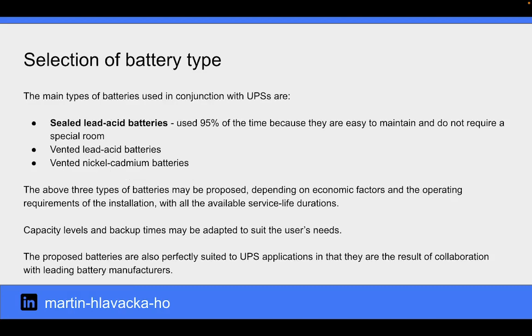The main types of batteries used in conjunction with UPSs are sealed lead acid batteries, which are used 95% of the time because they are easy to maintain and do not require a special room, vented lead acid batteries, and vented nickel cadmium batteries. The above three types of batteries may be proposed depending on economic factors and the operating requirements of the installation, with all the available service life durations. Capacity levels and backup times may be adapted to suit the user's needs. The proposed batteries are also perfectly suited to UPS application in the sense that they are the result of collaboration with leading battery manufacturers.